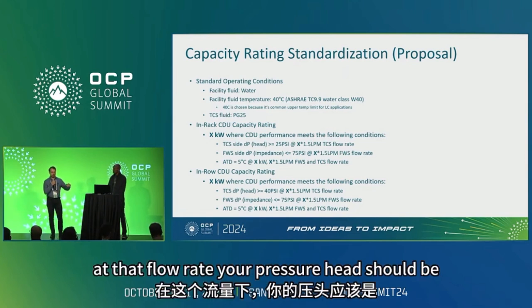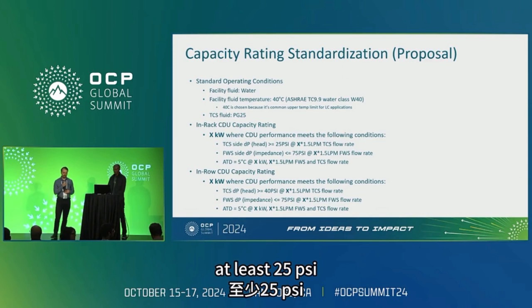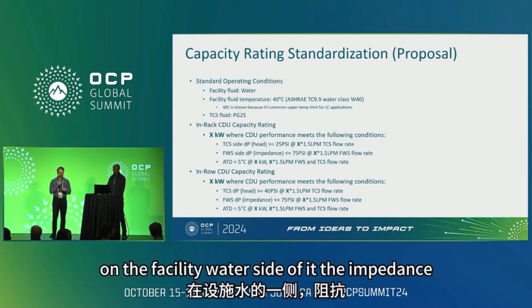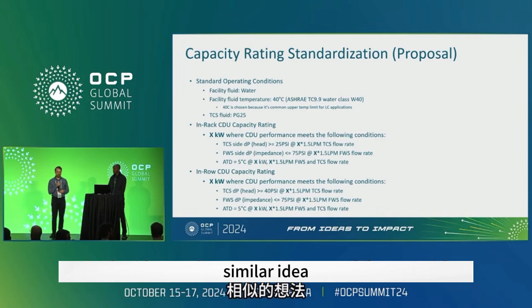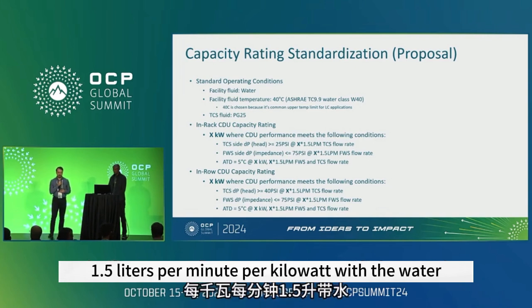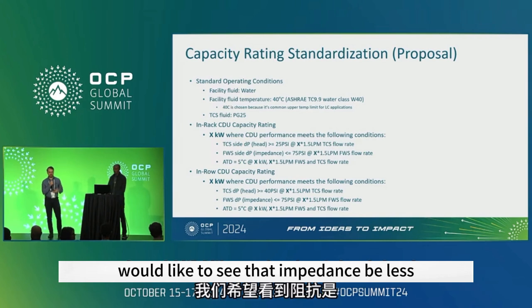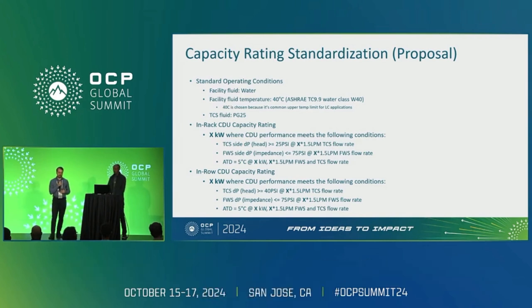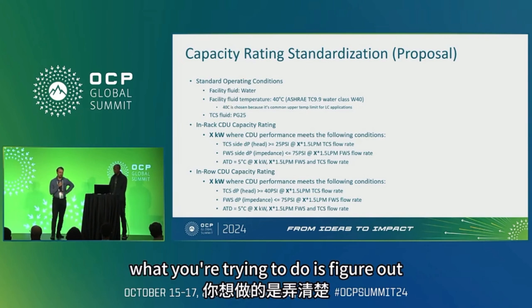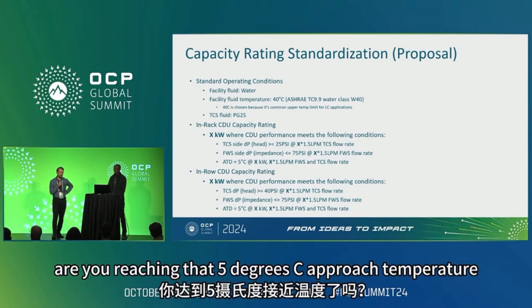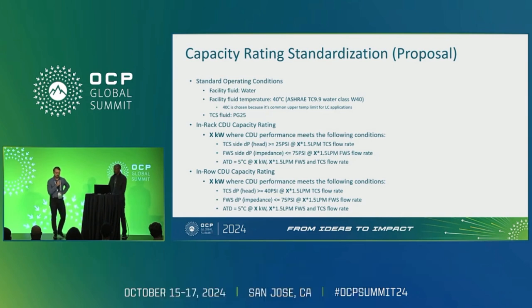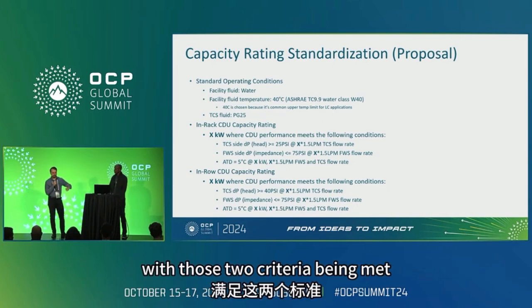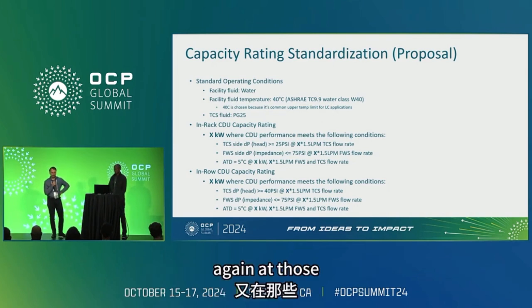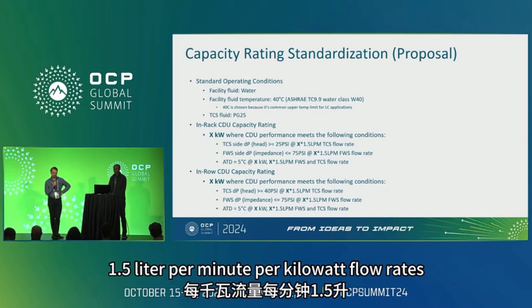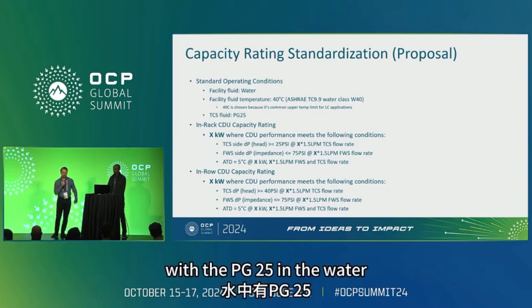And so again, at that flow rate, your pressure head should be at least 25 psi. On the facility water side of it, the impedance, similar idea, 1.5 liters per minute per kilowatt with the water, and we would like to see that impedance be less than or equal to 75 psi. And really what you're trying to do is figure out at what heat load are you reaching that 5 degrees C approach temperature difference, which is a very common target as well for the industry, with those two criteria being met. Again, at those 1.5 liter per minute per kilowatt flow rates with the PG25 and the water.